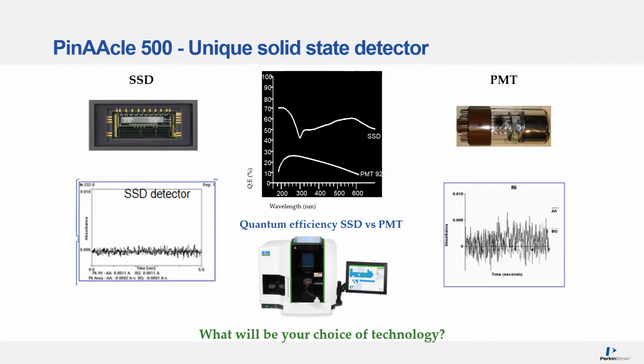We can even illustrate this looking at an example of nickel at 232 nanometers. Now, the picture on the left is a real-time signal of the nickel, but using the solid-state detector. You can see the scale on both of these, the one on the left and the one on the right, is the same. So we're going from 0 to an absorbance of 0.01. The noise coming from the photomultiplier tube system is far greater in amplitude than the one on the solid-state detector. So that should show you dramatically why this is a good development to have.